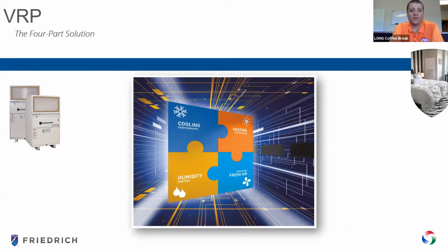And with the VRP unit, they're able to focus on all four primary things that we're worried about when it comes to maintaining a comfortable space, and that's whether it's cooling in the summer, heating, bringing in fresh outside air, which is becoming more and more important in our industry every day, and also humidity control. And while it's not always important in Colorado that we're so worried about humidity, it is something that they have an ability to monitor, which I'll get into a little bit later.